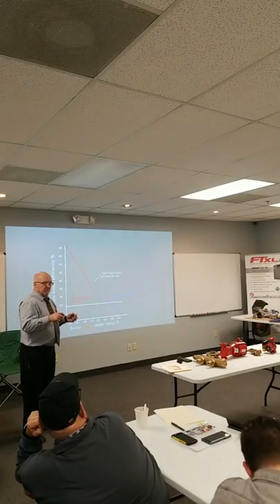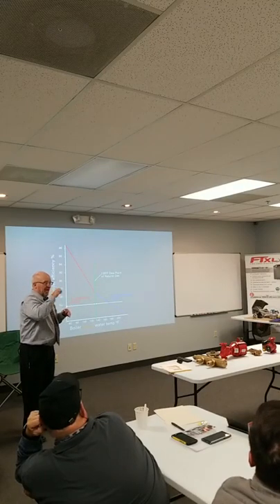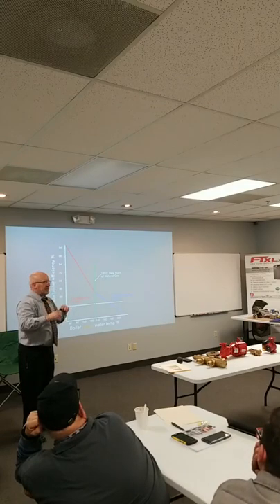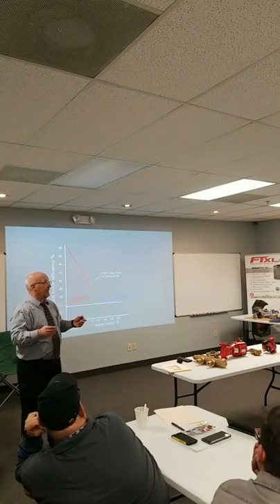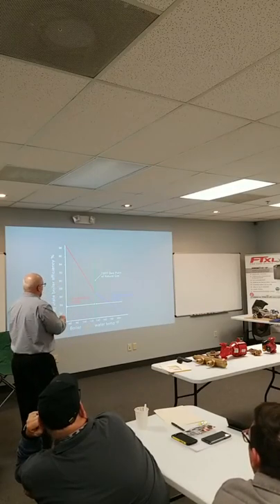So look at that 10 degree or 20 degree delta then. But remember, we're primary, secondary, okay? So I can take a 20 degree delta T on my system side and a 40 degree delta T in my boiler loop because I have independent systems. I'm getting ahead of myself. But there's a lot of things we can do with primary secondary, to the point where I would even tell you guys to pipe cast iron boilers primary secondary, quite honestly, because you could take different delta Ts through. But let's get back to the chart.